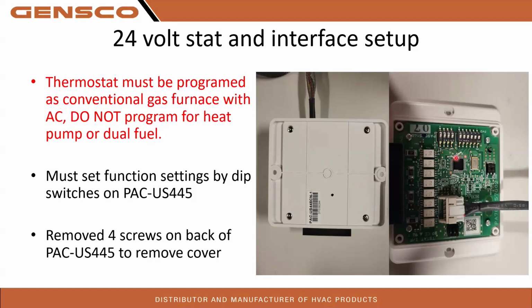Same thing on SVZs or any other of our equipment that you may be using these on. These dip switches are going to need to be set up. The only exception to that is if you're using City Multi indoor equipment, all your function settings for those will be done using dip switches on the equipment. But for everything else, these dip switches will need to be adjusted. So make sure you look at your installation manual for the PAC 445 and whatever your system requirements may be for that.